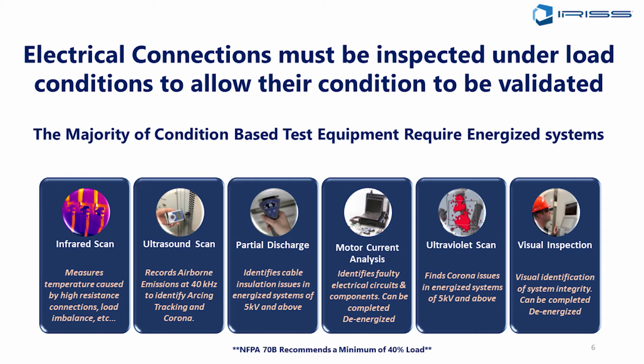Motor current analysis, our friends from PDMA are going to talk to that at length. So motor current signature analysis essentially allows you to look at different characteristics of the motor, both de-energized and energized. What are the voltage and current waveforms versus a normal parameter for a given motor, right? So it allows you to trend different data points, and from that identify rotor problems, stator problems, winding problems. All of these will have different signature patterns that will show up in your motor current signature analysis software.